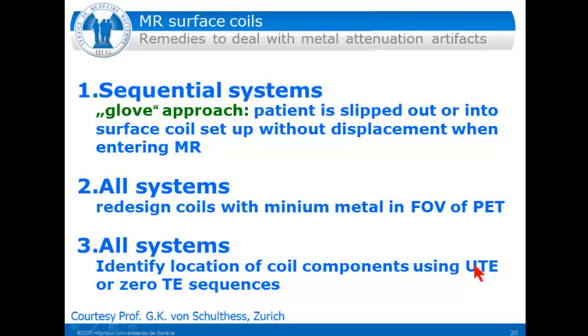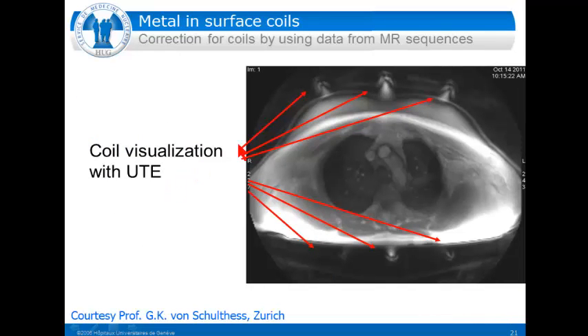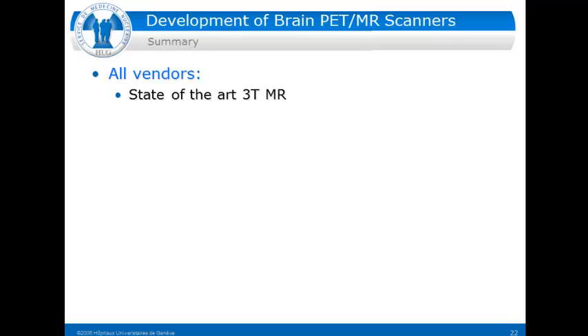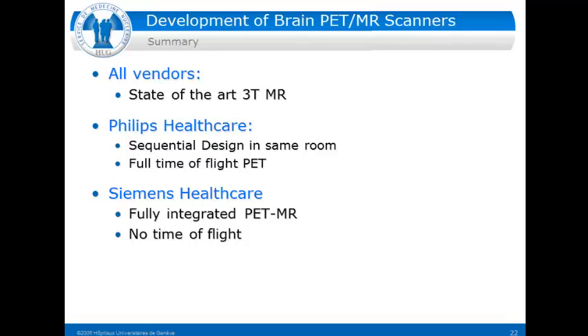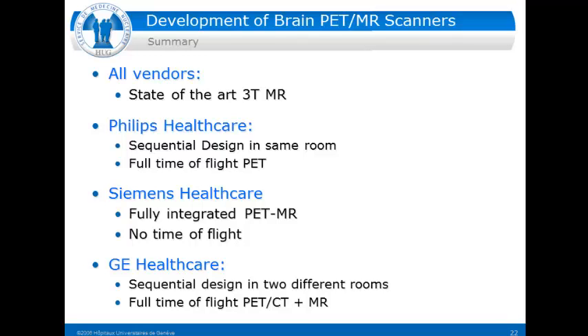In all systems, the location of coil components can be identified using UTE or zero-TE sequences. Here is one example of a UTE sequence on a chest: the MR of the chest is shown, the metal parts of the coils are visible, and once seen by the UTE they can be corrected for. In summary: all vendors use state-of-the-art three Tesla MR scanners. Philips has a sequential design in the same room allowing full time-of-flight PET. Siemens is currently the only vendor with a fully integrated PET-MR but without time-of-flight. GE has a sequential design in two rooms permitting full time-of-flight PET-CT and MR, though with two strictly distinct systems.